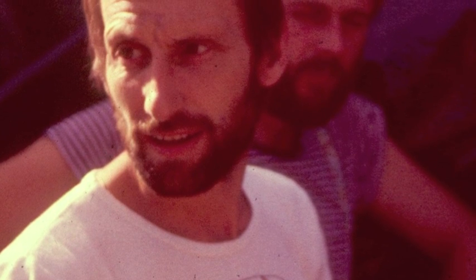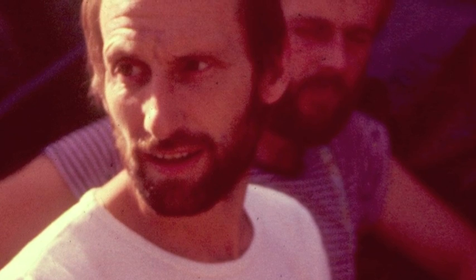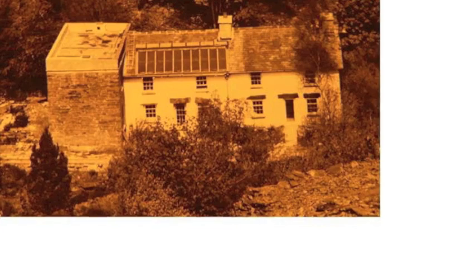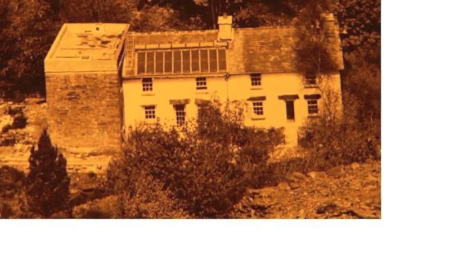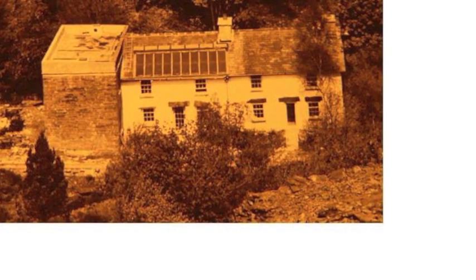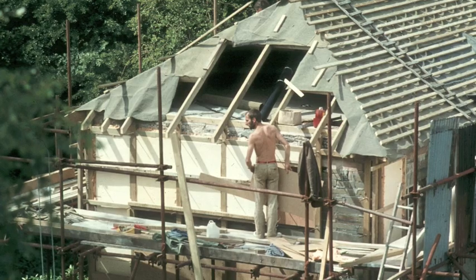A Trombe wall wouldn't work in the UK because it had been tried at Bebington, so we realised we had to do something different in our climate. So it was actually an air heater, a solar air heater, but you passed the warm air down the front of the cottage wall, so that was the thermal store. It was quite sophisticated really, but it had one basic problem in that the whole of the wall faced a hill, so got very little sun.